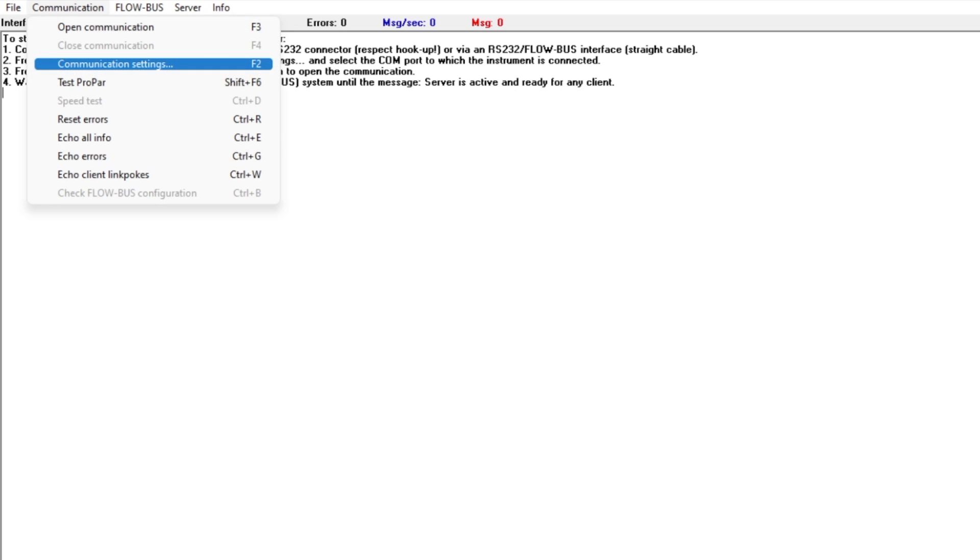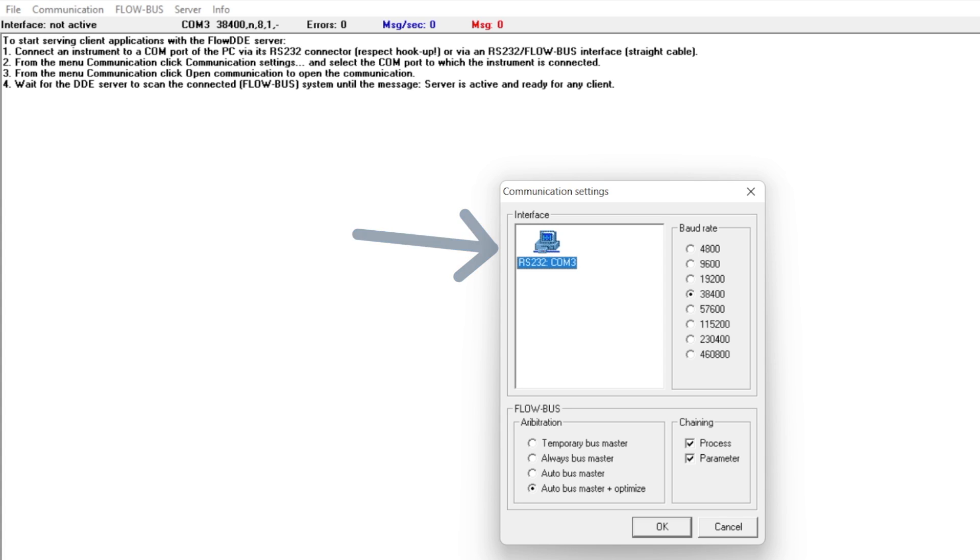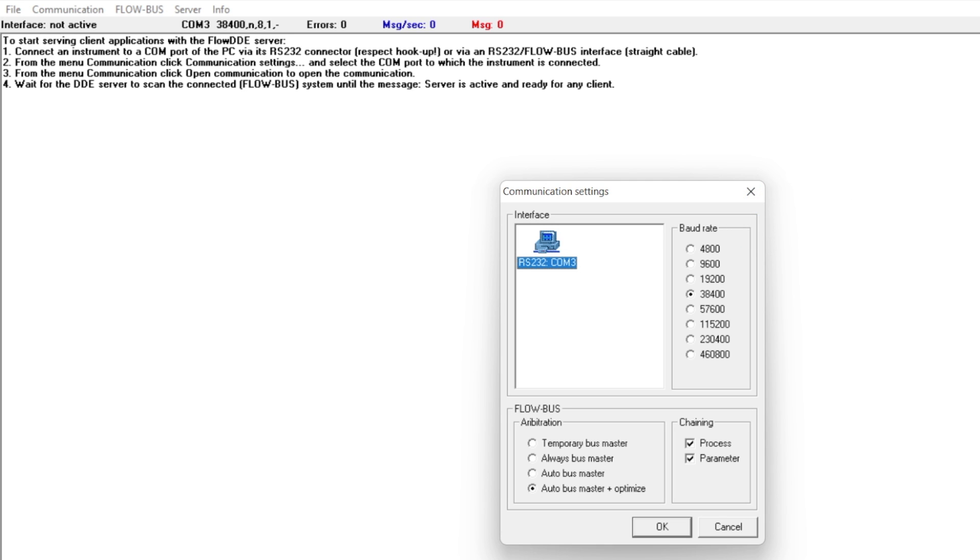The first thing you'll need to do once the flow meter is plugged into your computer is click on communication settings under the communication menu. In the dialog box that pops up, you can choose the COM port that your flow meter is connected to. In my case, this is COM 3. You can confirm this in the device manager on your computer. You'll also need to choose the baud rate. The default is 38400 and this is perfect for this flow meter. You will likely not have to change it.